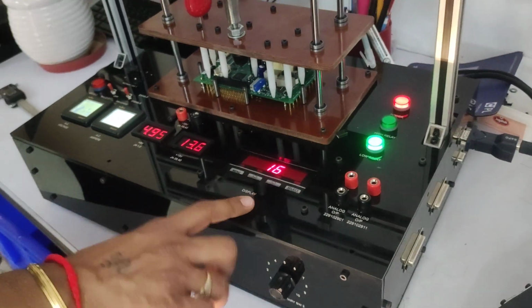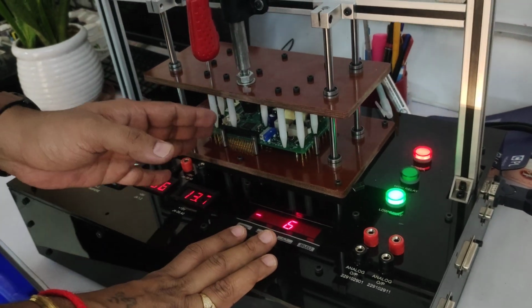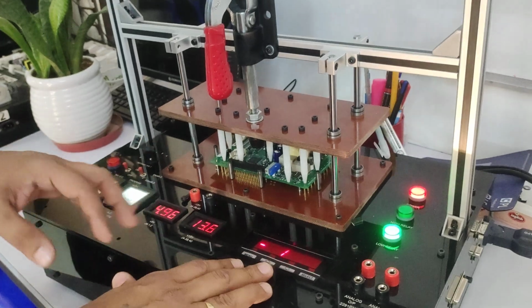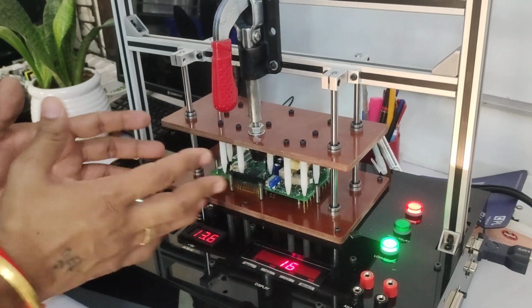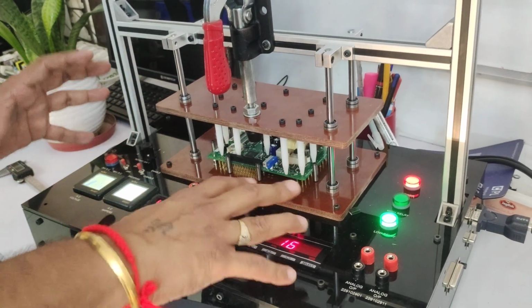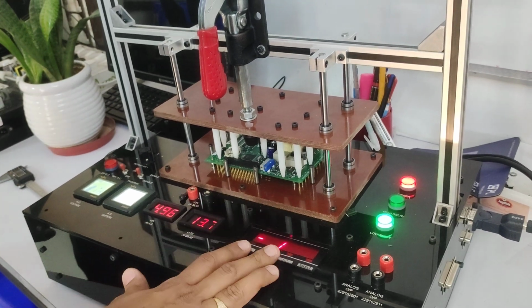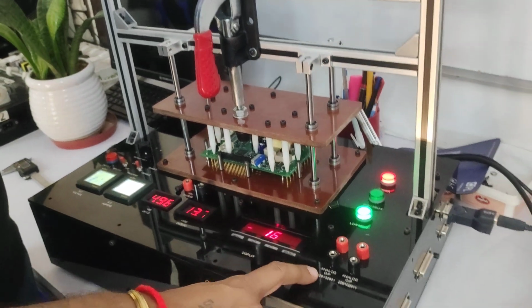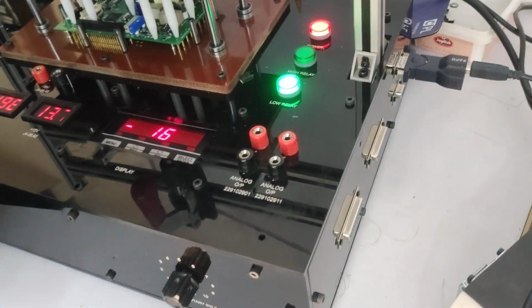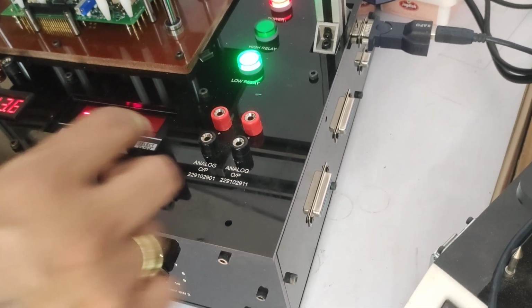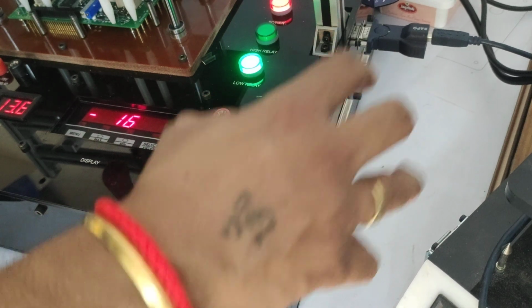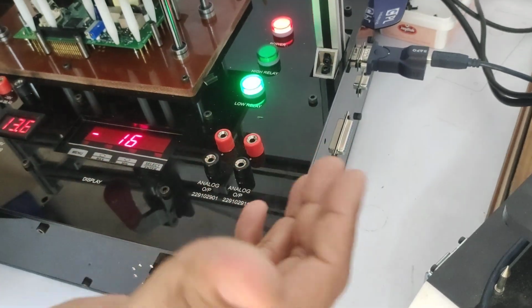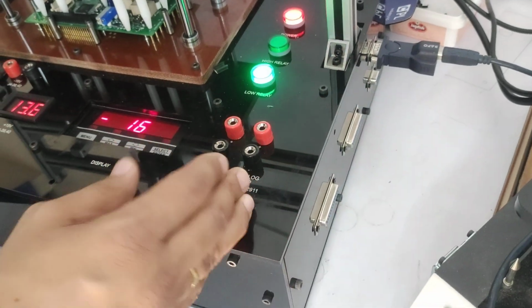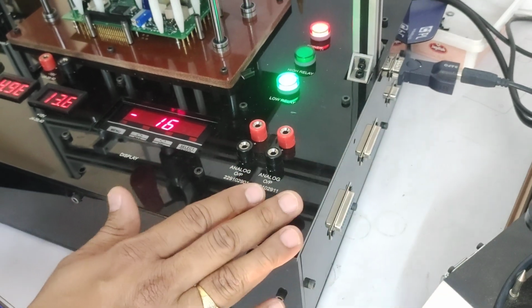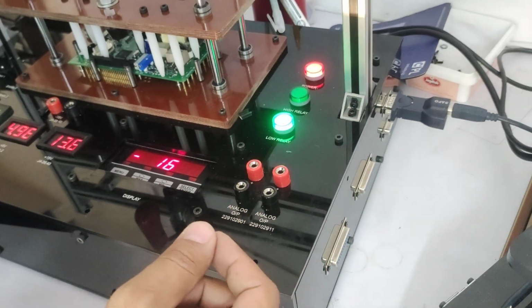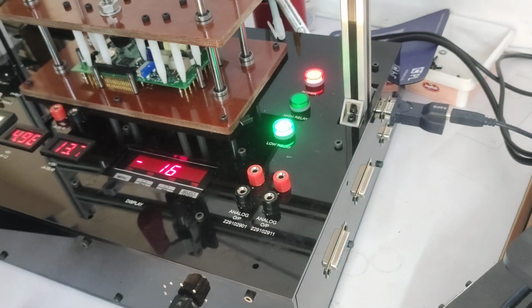This is the display part. From there, this particular PCB is controlled, and lots of other test functions are executed from this display. This is an ampere measurement. They need very precise amperes, down to microamperes. So we suggested having an external multimeter, a standard Fluke or from any other company, which you can attach externally to measure the required microamperes.